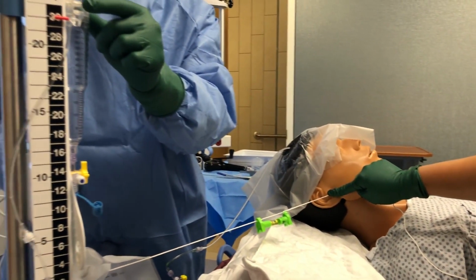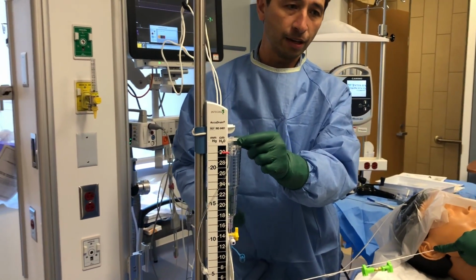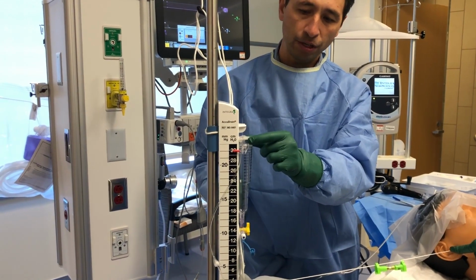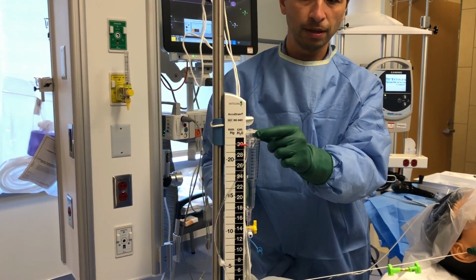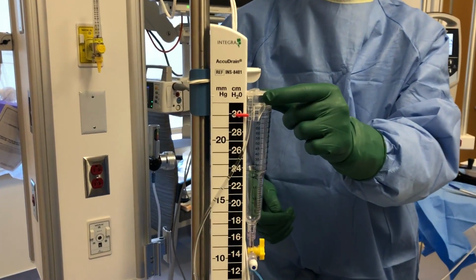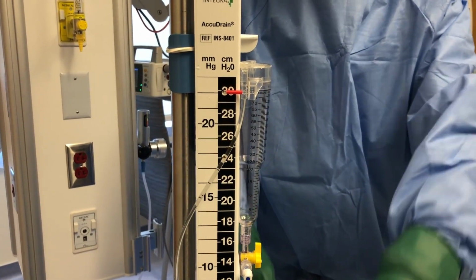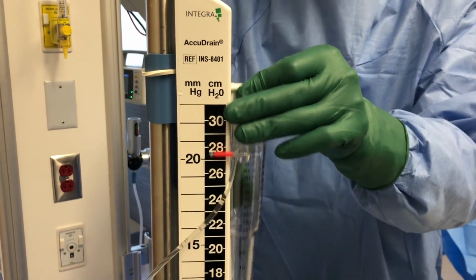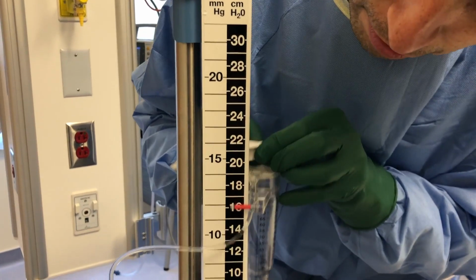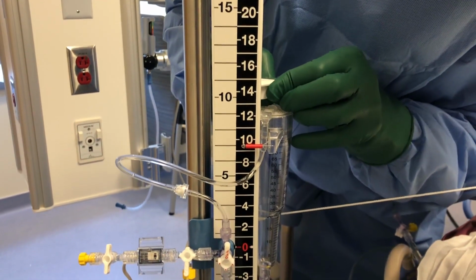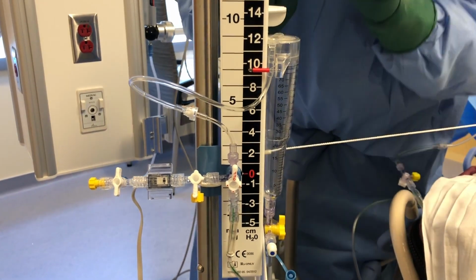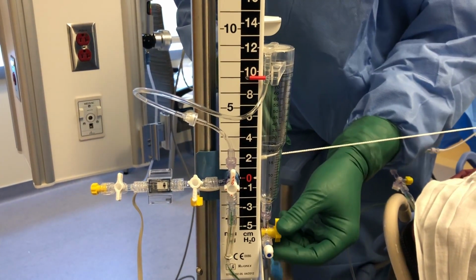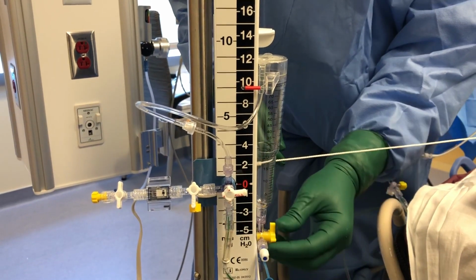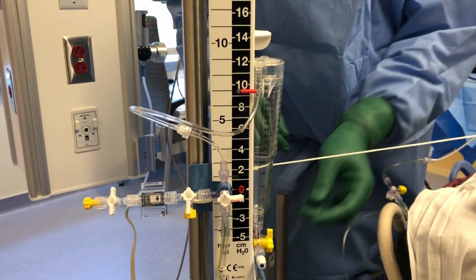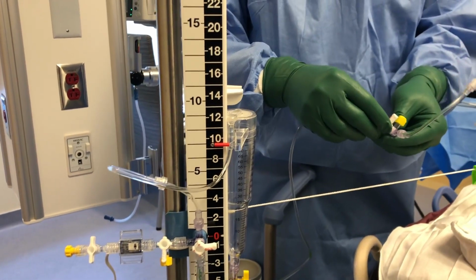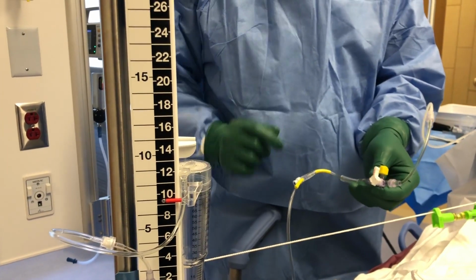And then the chamber needs to be at a level so that we drain it at a certain pressure. The pressure that we normally specify is measured in centimeters of water, traditionally, although it also has markings for millimeters of mercury. So when we set this up, typically we would then lower this chamber to, for example, 10 centimeters. And we should then be able to open up all the channels and open up the channel at the connection as well, and see egress of the CSF.